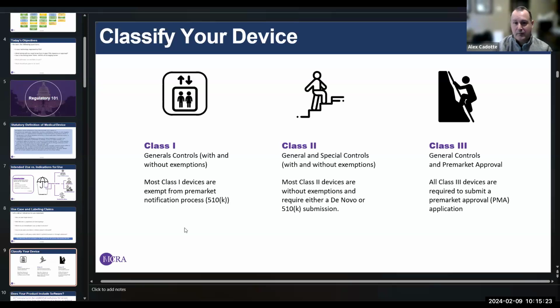Ironically enough, with AI machine learning, and that's part of why the US regulatory system is a bit challenging sometimes, you may have a really amazing technology and you may be able to do a 510K for it, but you have to spend a good amount of your time during the 510K for your innovative device explaining to FDA why it's the same as something somebody else did. So that's kind of the regulatory mechanism for class 2 devices.